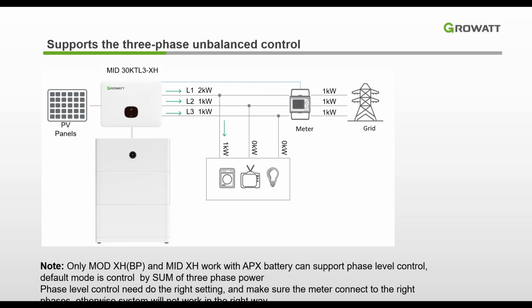So this 3-phase unbalanced function is also useful for that. Here's an example. For the MID 30 kilowatt inverter, we require a 3 kilowatt export limiter. In that case, if your load is using 1 kilowatt from one of the phases, then you can see on the picture, 2 kilowatt on phase 1 provides 1 kilowatt to your loads and 1 kilowatt to your grid, and the rest of your phases, L2 and L3, will just generate 1 kilowatt each, so it will all export to your grid. So that means we provide 100% unbalanced power.